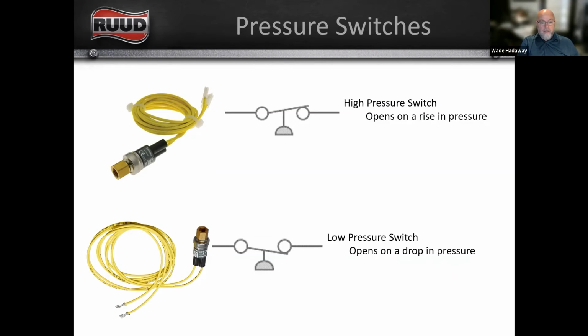Whereas the diagram on the bottom is a low pressure switch, and as that pressure drops, that switch opens. So you can tell just from looking at the diagram whether it's a high pressure or a low pressure switch, based on which way the switch can open and which way that pressure icon would be able to move, right? Whether it can move up or whether it can move down. It can't go through that circle that indicates your wire connection, right? Or the other side of the switch.